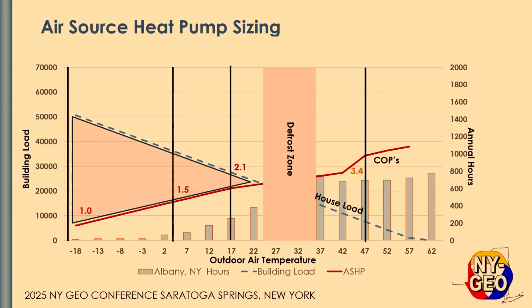This is a slightly different looking chart, but you can see the load line here is that blue dotted line, the heating load line, and outdoor temperature is here, and the bars represent the hours of operation. This is actually Albany, New York, so I've done the presentation more about local weather. You can see we still have a few hours clear down to minus 18, minus 13, minus 8, but most of the hours are really above the 12 degree bin temperature there.